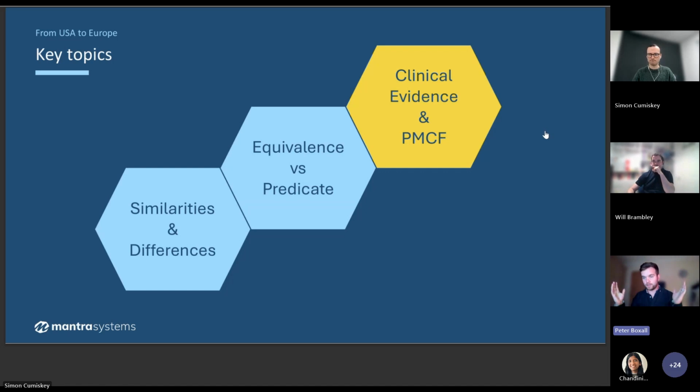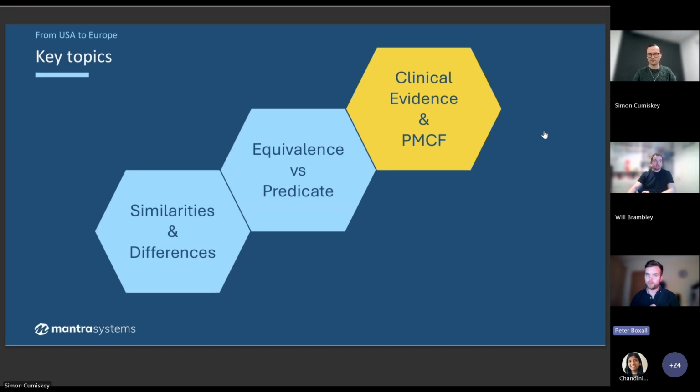Once we've assessed the clinical evidence relating to our own device, we can write a post-market clinical follow-up plan and conduct a survey or a study to assess continued performance and safety and look out for anything new that's come to light. So this is the general process, and hopefully that's provided a good overall description of where you need to use clinical evidence.